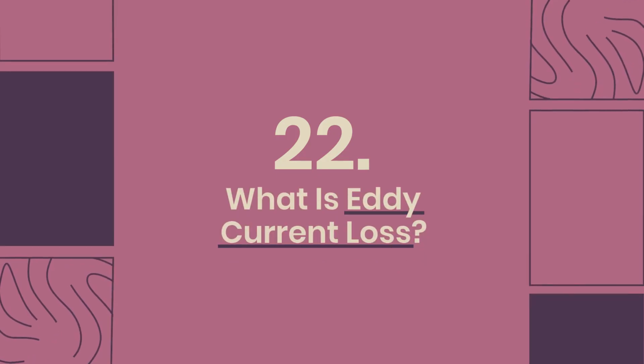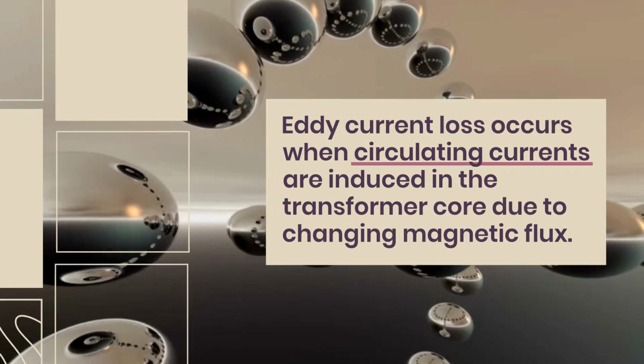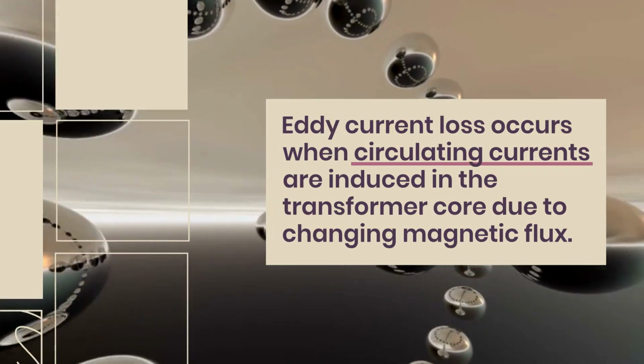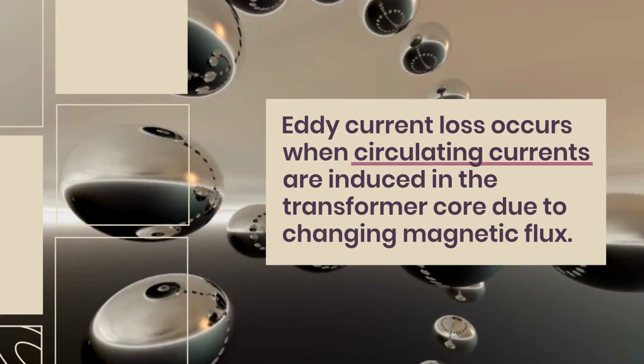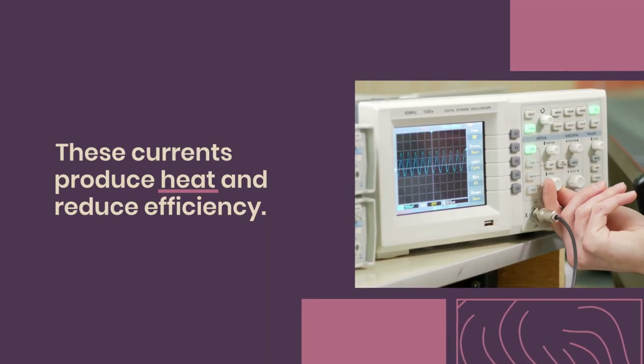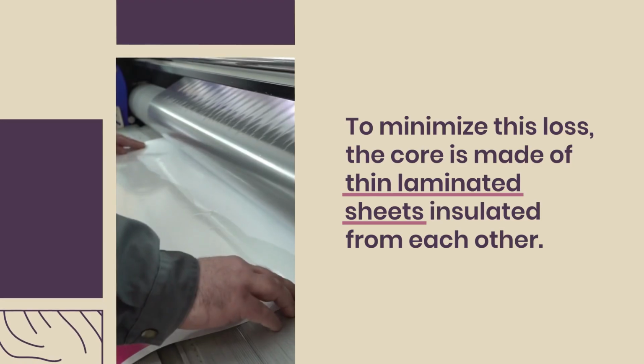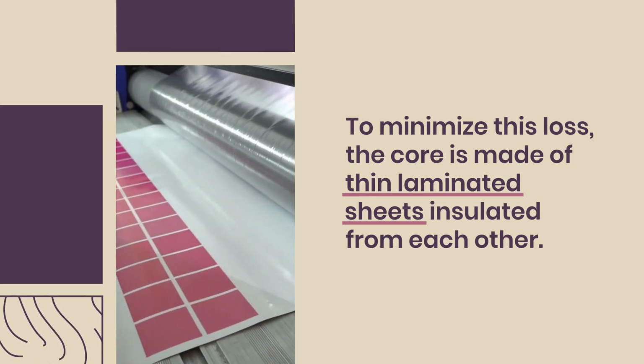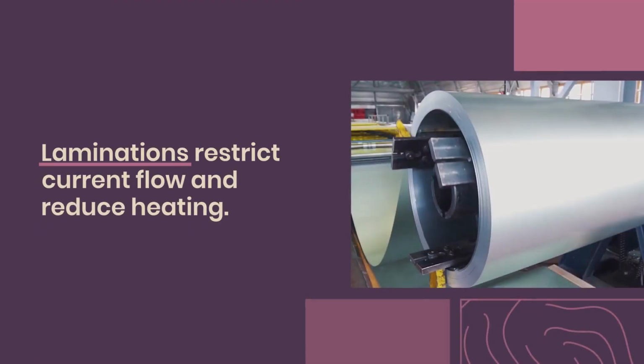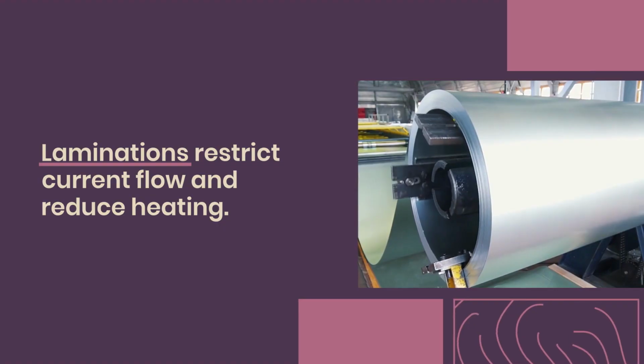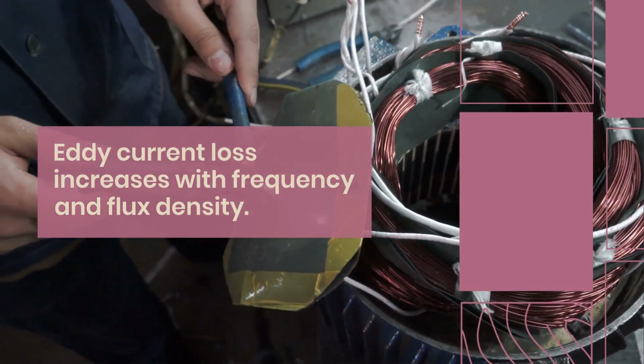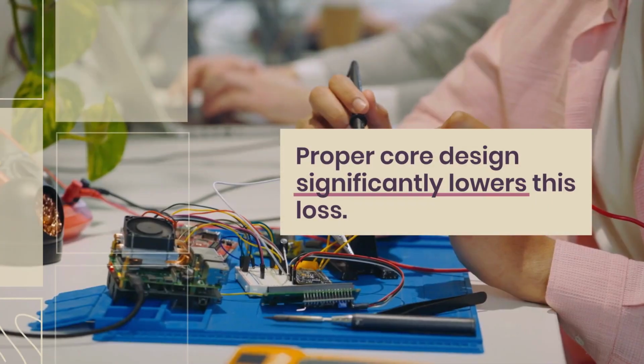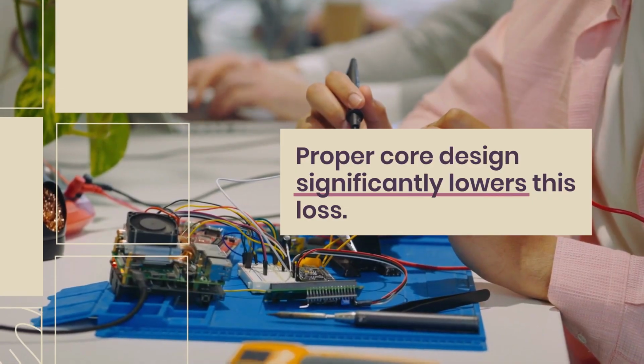22. What is eddy current loss? Eddy current loss occurs when circulating currents are induced in the transformer core due to changing magnetic flux. These currents produce heat and reduce efficiency. To minimize this loss, the core is made of thin laminated sheets insulated from each other. Laminations restrict current flow and reduce heating. Eddy current loss increases with frequency and flux density. Proper core design significantly lowers this loss.